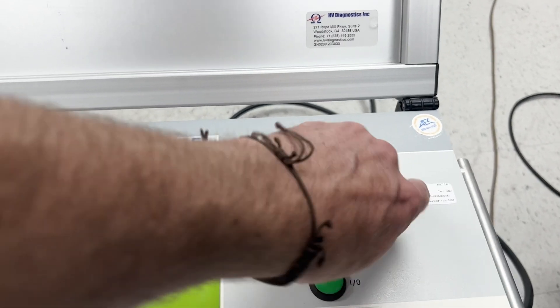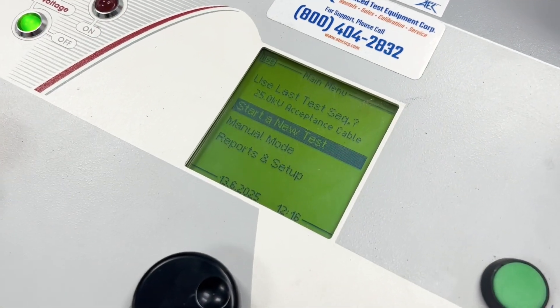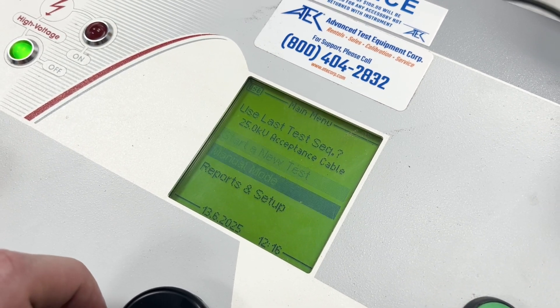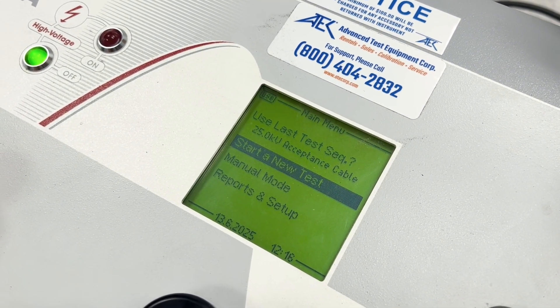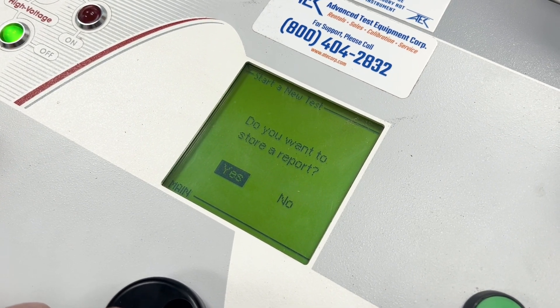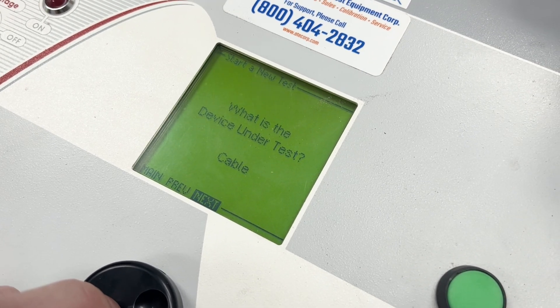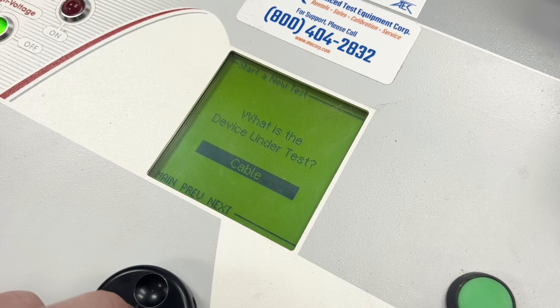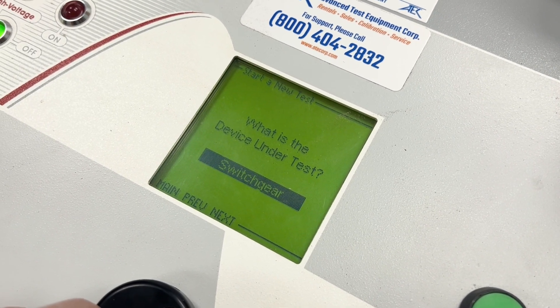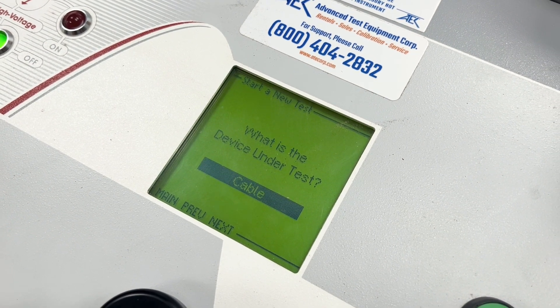We're going to turn this on and go through the settings. Here we are on the main menu where you can start your test, manual mode, reports and setup, or use the last test sequence. We're going to test the cable, but you can see what other things you can test like motor, generator, transformer, switchgear, vacuum bottle, or something else. I'll keep it on cable.